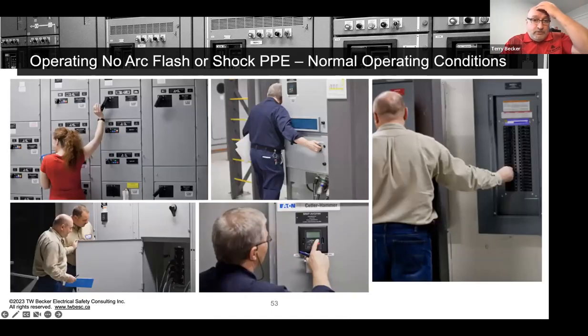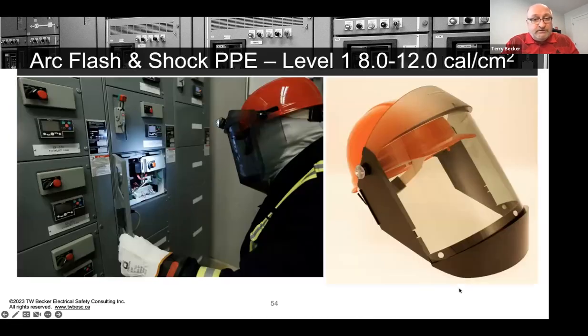So, operating electrical equipment, just some pictures here. Under normal equipment conditions, the worker that's authorized can operate the equipment procedurally: stand to the side, look away, might want to hold your breath, then switch it and you're done. Open or close that. You can read an HMI or display. You don't need arc flash PPE. We need to get beyond some of these myths.